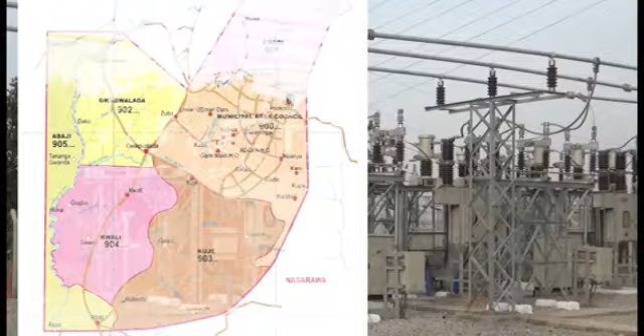Mr. Mohammed, during the event, said the 100 MVA was added to the old 120 MVA capacity at Katampe: The existing capacity in Katampe is 120 megawatts. With this addition of 100 megawatts, it means that the capacity of Katampe has increased to 220 megawatts. So with that development, it means that we have met the N-1 criteria here in Katampe, meaning if one transformer fails in Katampe, the society will not feel it. That means Abuja Disco will not lose electricity because one of them has failed.